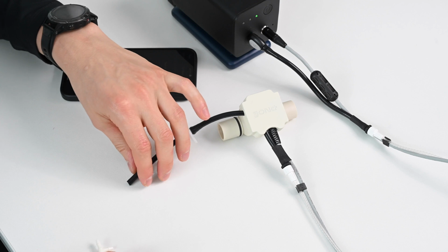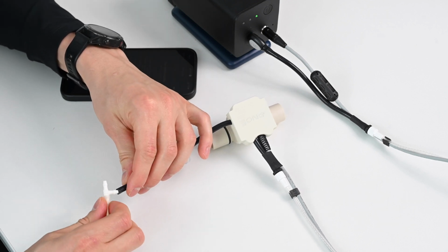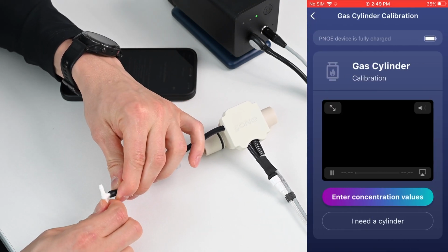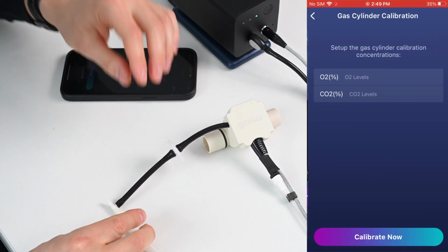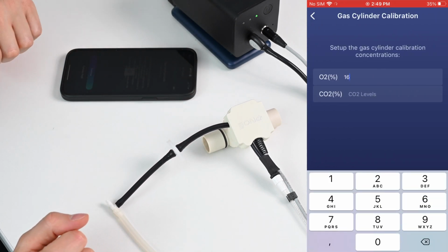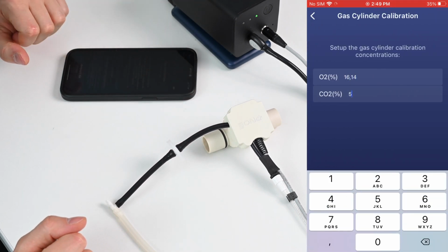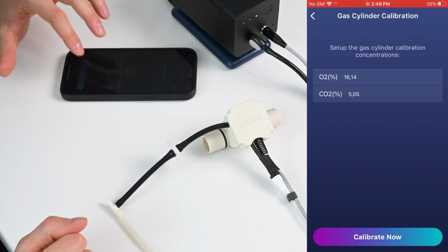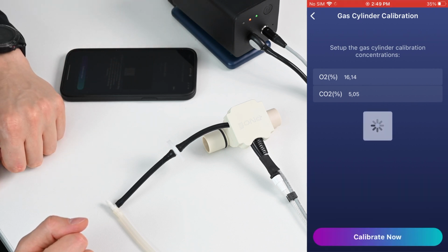The other method to perform a calibration is with a gas cylinder. To perform a gas cylinder calibration, you will input the exact values of the O2 and CO2 values stated on the spec sheet that arrived with your gas cylinder in the fields asked by the app.